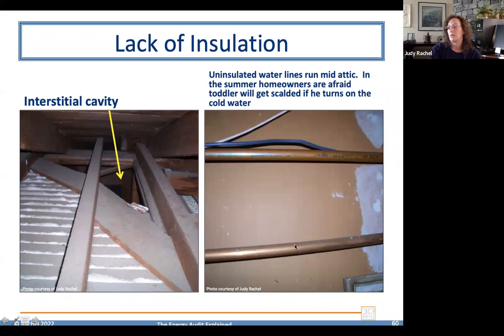The plumbing was run fairly high in the attic. And during the summer, the homeowners basically never got cold water. The water lines were getting so warmed by the attic air that they were never getting cold water, and they had a toddler, and often the water was pretty darn scalding. So they definitely wanted to know why it was they couldn't get cold water in the summer. And that was a pretty simple thing to figure out.